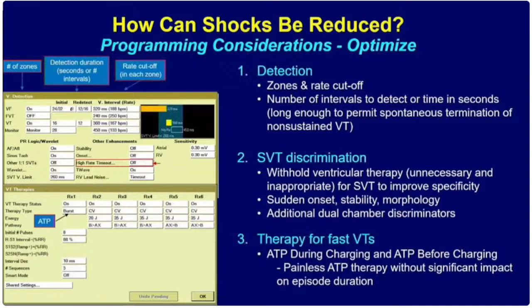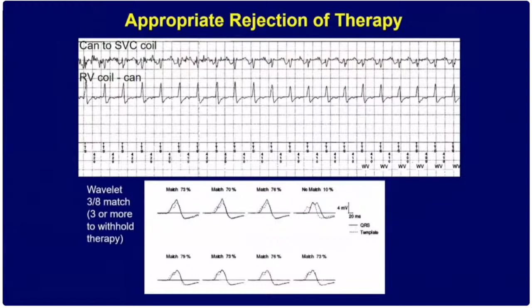This is just an example of where the device appropriately used wavelet, and each manufacturer has their own algorithm for how it looks at this and counts beats. But if you have at least 3 of them that match, it'll withhold therapy. So if it's 70% or more in this case that matches the stored signal, it's going to say it's SVT. I don't want to treat that as VTAC, I'm going to withhold therapy.